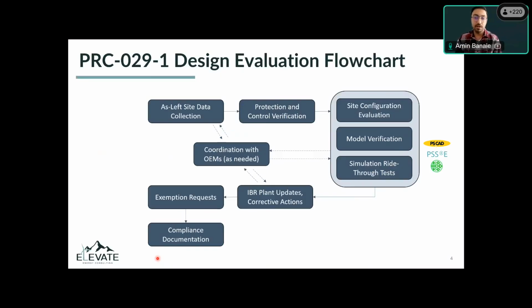So at Elevate, how we do PRC-029 is firstly the design evaluation part, which involves several steps, and they're shown here. One first step, which is very important, is to gather as much data as is available about that IBR site. And once that data is available and something is not there, we're going to coordinate with the OEMs to find out if we can have that information that's needed for doing a PRC-029 study. And then we're going to do a very quick check about different settings or information that we have and see if the IBR model has those settings implemented correctly.